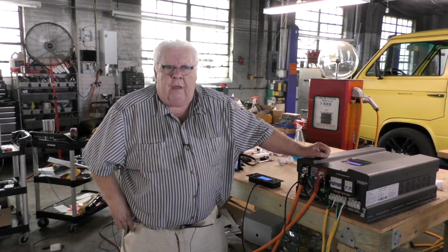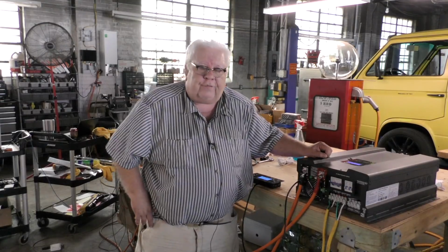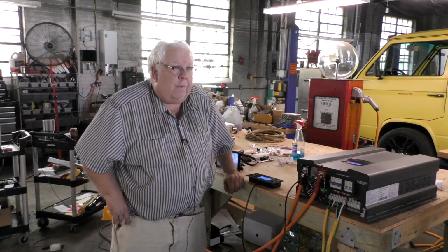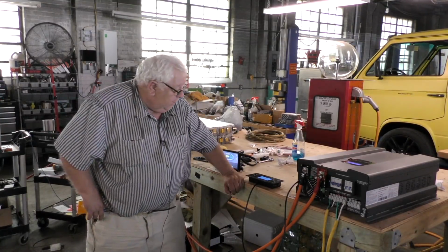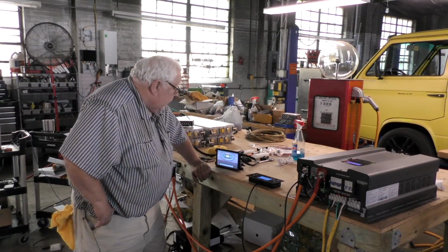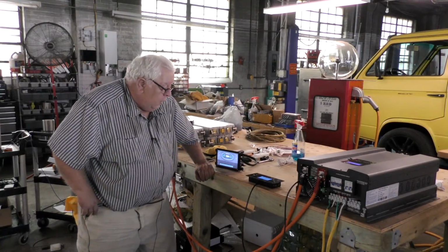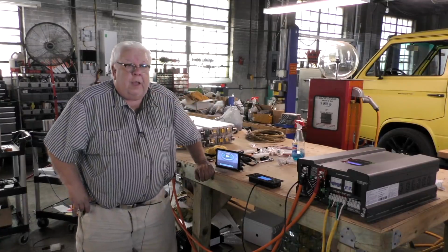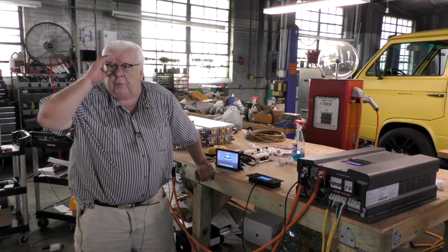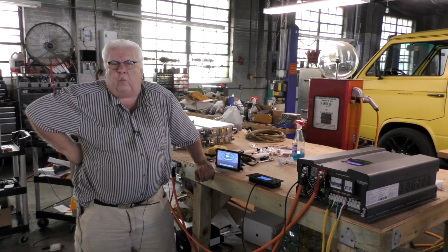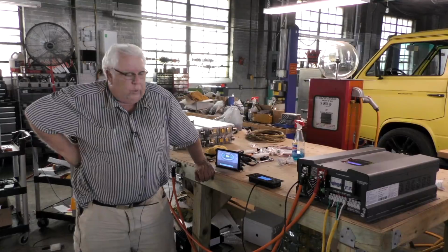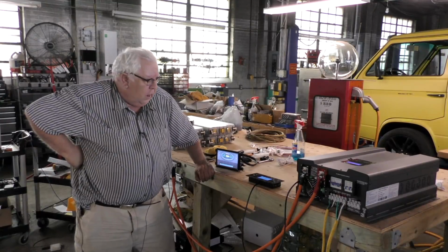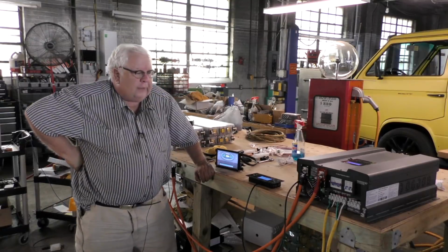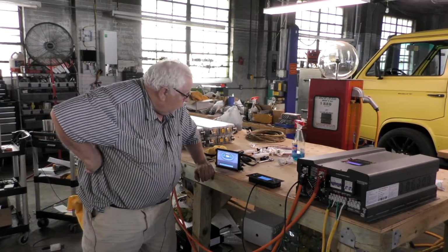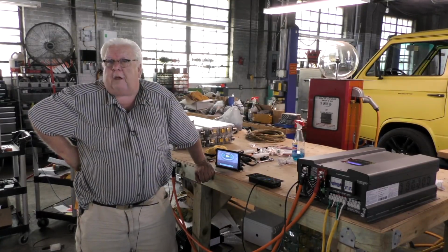And we've just brought up maybe our DC fan a little louder. It has 2 in the front for the transformer and 1 here, and they are kind of controlled by temperature, and so that's working pretty good. And I'm at 99 amps, and that's at 44 volts is 4,400 watts. Our shop's doing about 4,200. So I'm doing about 8,000 watts on 4 Solar Edge grid ties. They're operating the entire shop and generating 4,000 watts of charge into our battery, which is now at 44%. Let's go fire up number 5 and see what happens.